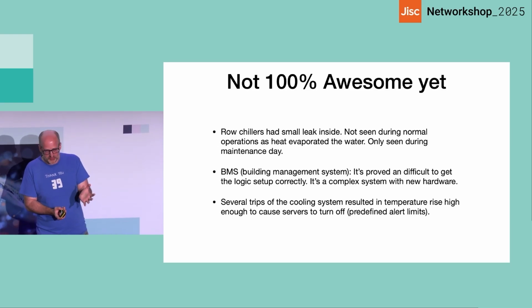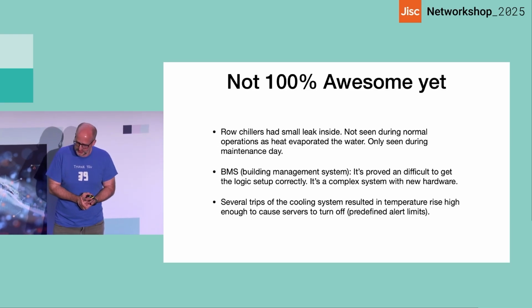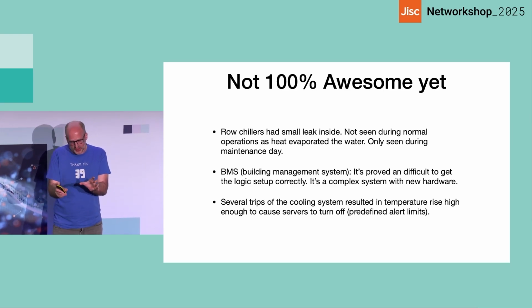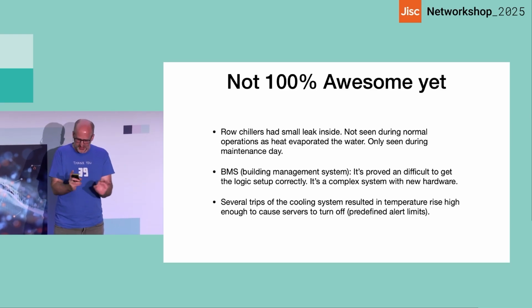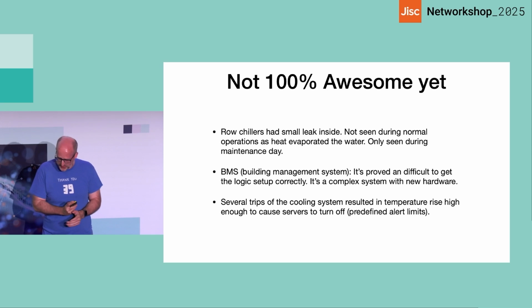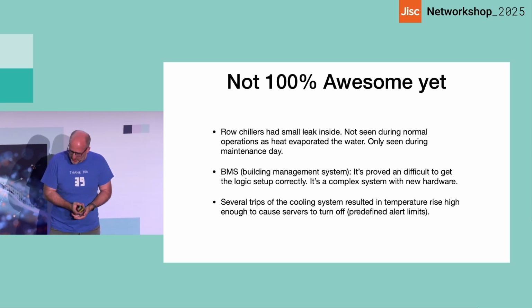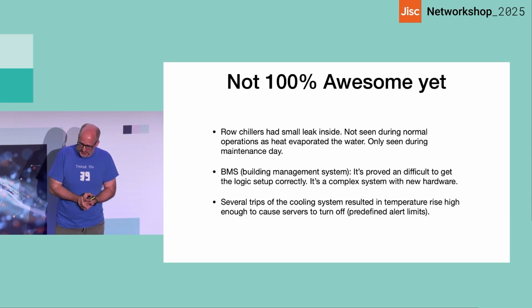We have had one leak within one of the in-row chillers, which wasn't very nice. We only saw it once we had a maintenance day that turned off the heat from the computers, because otherwise the leak was at such a low level that it was just evaporating off. It's proved difficult to get the building management system to manage the heat pumps accurately. The heat pumps occasionally send error messages, and dealing with these non-standard situations has proved complex, but we've been getting there. As a result, we had a few trips that had seen high temperature rises. We prepared for this. We have a system that turns off the cluster if it gets too hot.